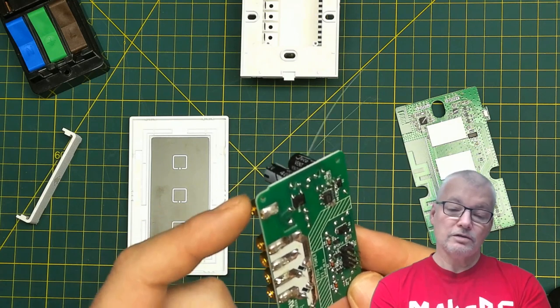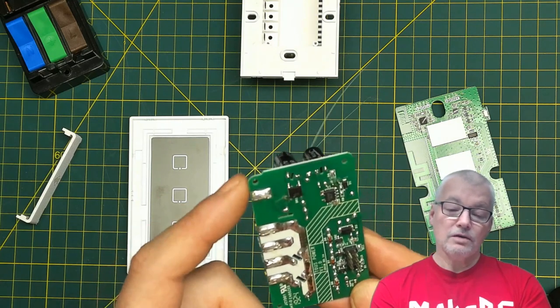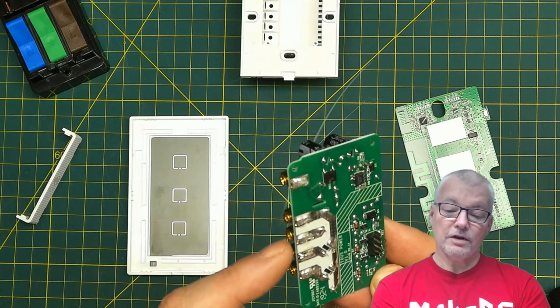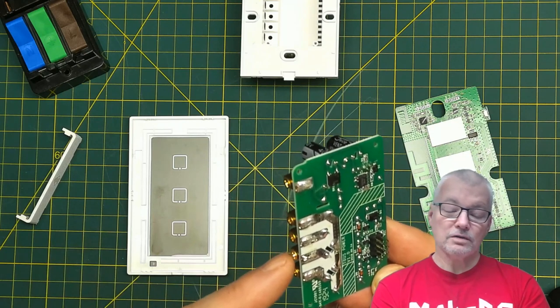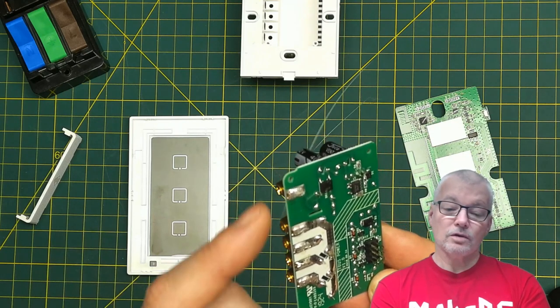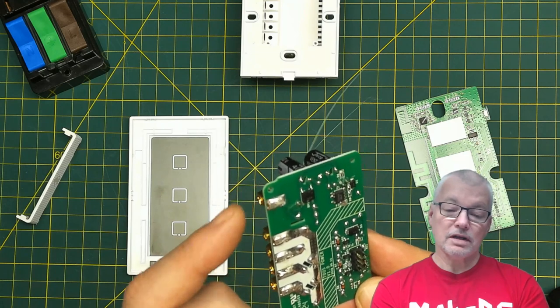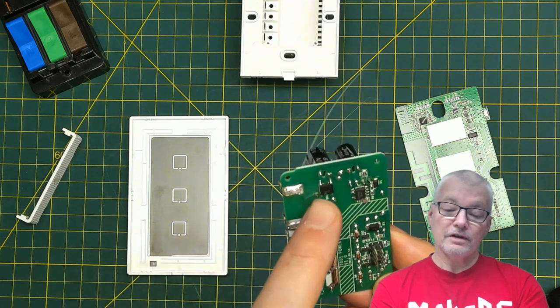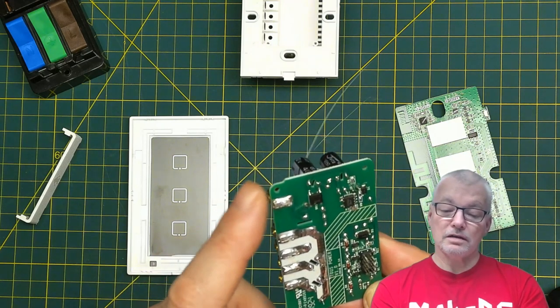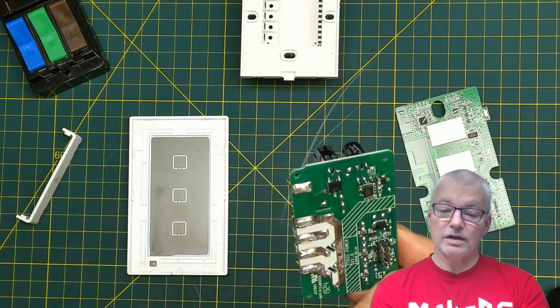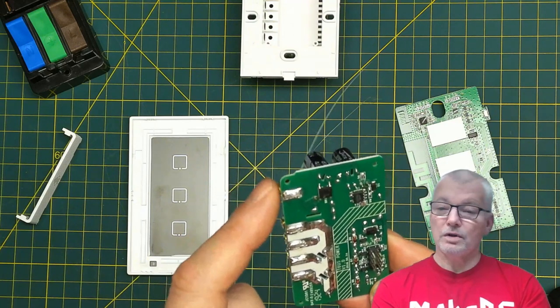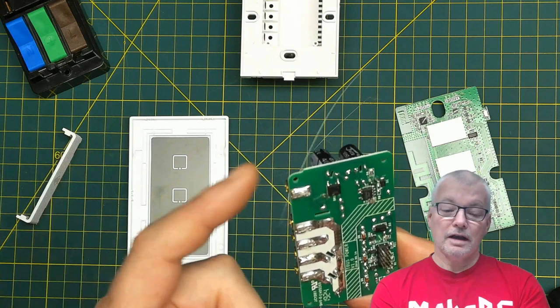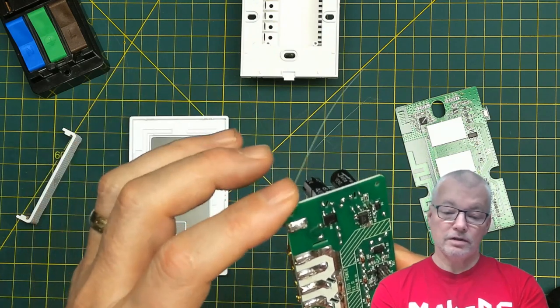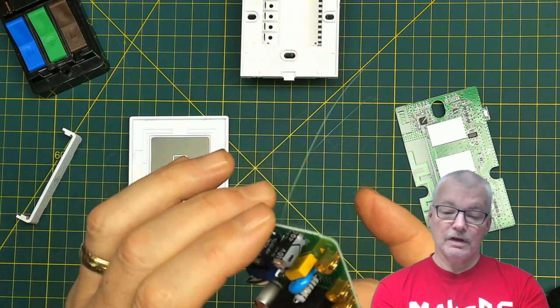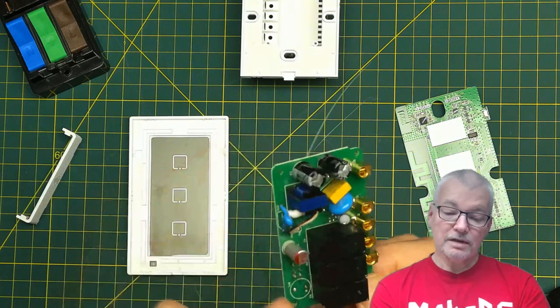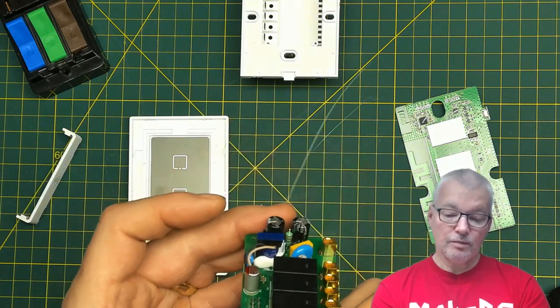And your neutral is way out of the way. Now, you can't bring your three lives going out to your loads, you can't bring the neutrals all back to here because, as you can see, there are very, very thin traces here. This is only here to provide the power for the internal module. So your grouping of your neutral should be done external to this light switch, not within it. And that's pretty much all there is in here. So it looks pretty well built.